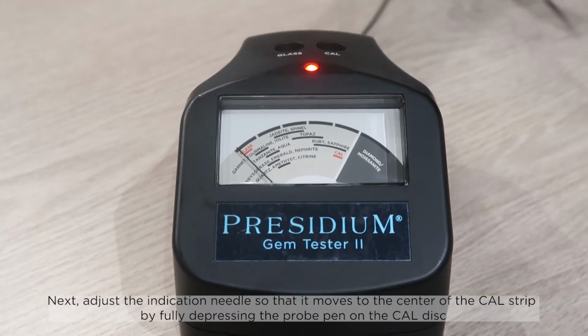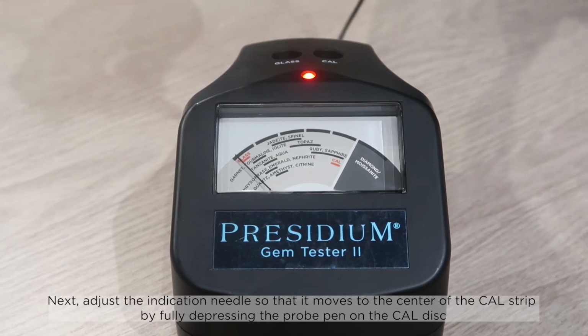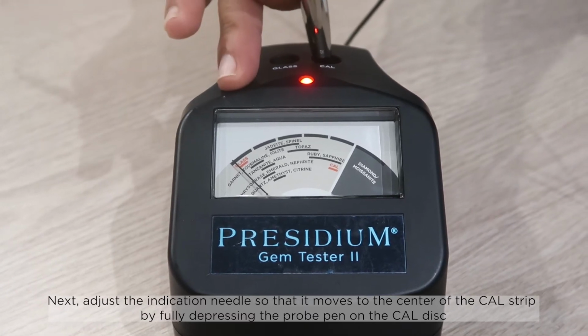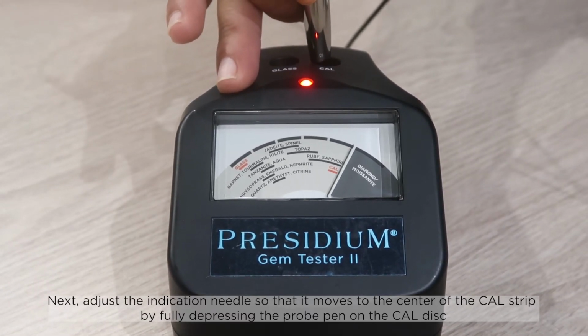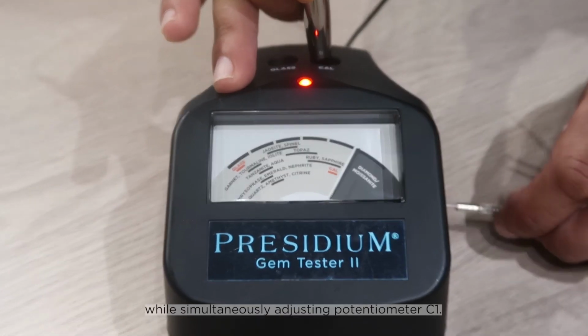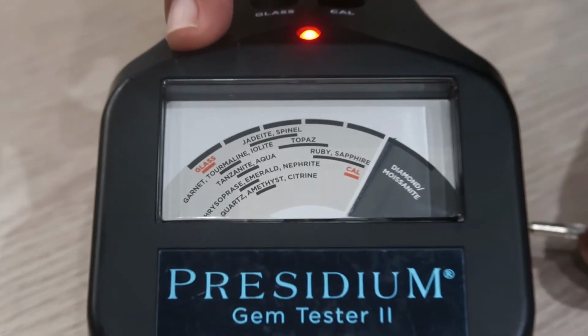Next, adjust the indication needle so that it moves to the center of the cal strip by fully depressing the probe pen on the cal disc while simultaneously adjusting potentiometer C1.